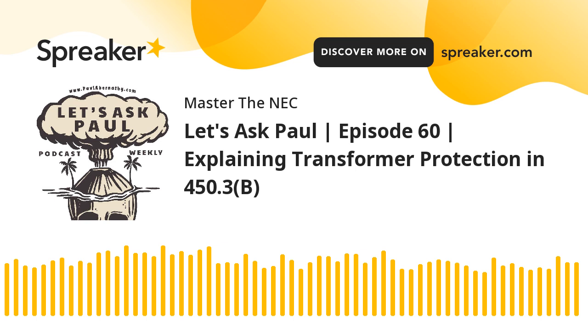Now, moving on, let's talk about the more common application, and we're talking about primary protection here, where I'm going to have the protection for a 45 kVA transformer. These are very common sizes, 45, 50, 75, 25. These are very common transformer sizes. And this lesson is going to apply to all of those. Doesn't matter. Same concept. We're using the VA value of that transformer to work it. Just know that 45 kVA is 45,000 VA, a 75 kVA is 75,000, a 25 kVA is 25,000. You plug it in the same way. It's the same math either way.